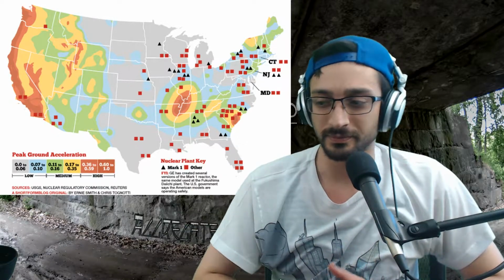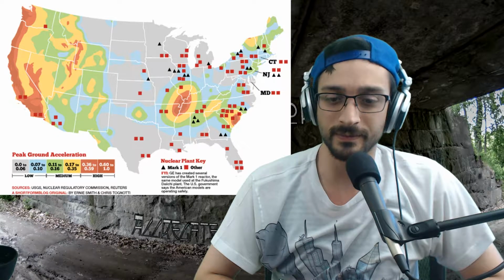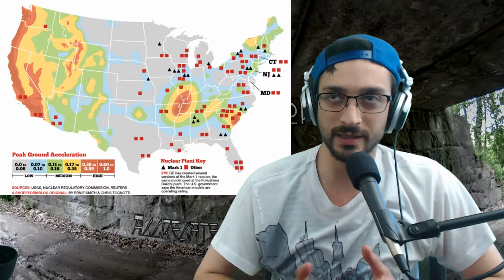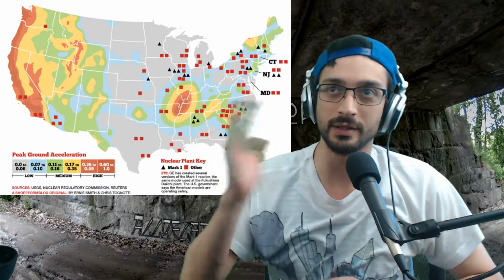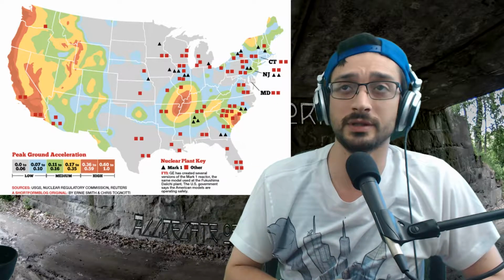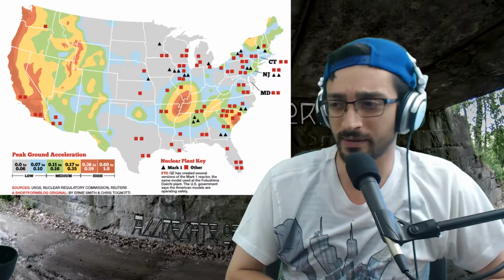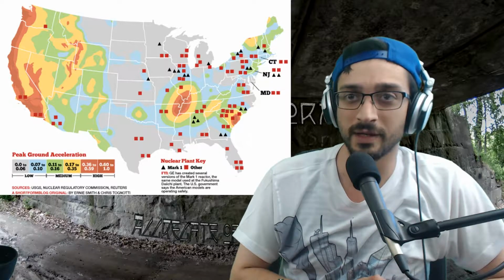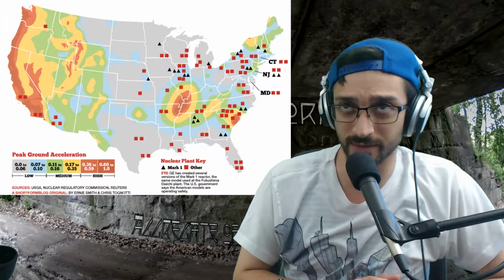Basically, when you design the structure of a building, there's certain design standards or certain coefficients you use in designing for the structure and how much you can sway. It'll determine what type of joints you use. It'll determine what kind of bracing you need. Even in New Hampshire, when I was doing fire protection systems, fire sprinkler systems and stuff, we would still have to seismically brace the sprinkler systems.